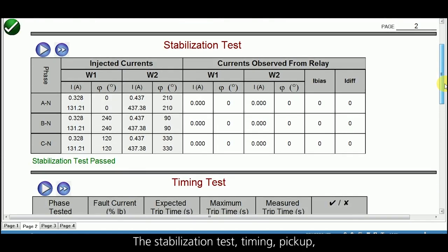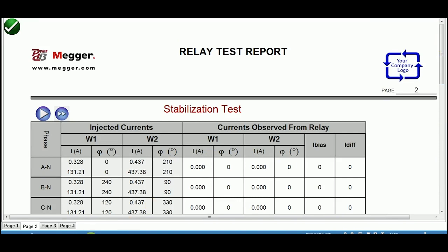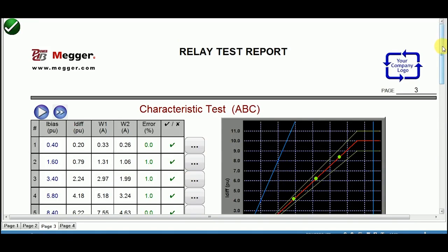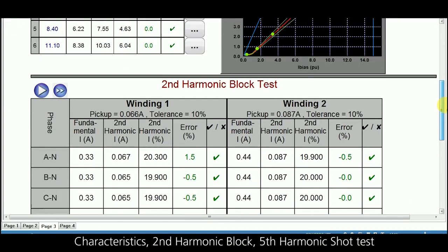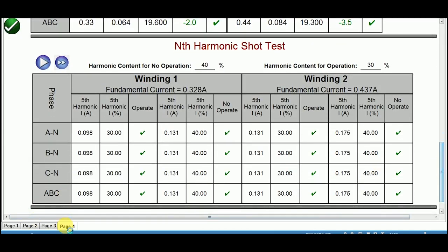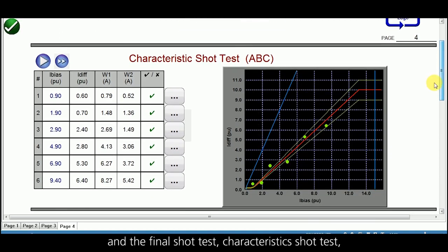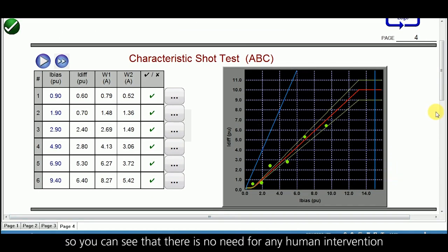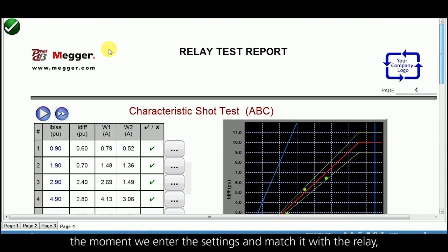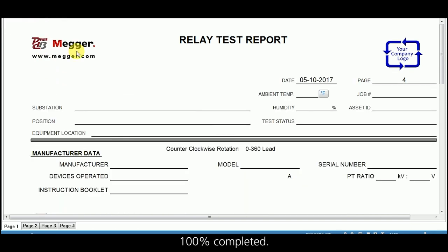The stabilization test, timing, pickup, characteristics, second harmonic block, fifth harmonic shot test, and the final characteristics short test — all have been completed. There is no need for any human intervention. The moment we enter the settings and match them with the relay, in the next 15 minutes your transformer differential relay is 100 percent tested and completed.